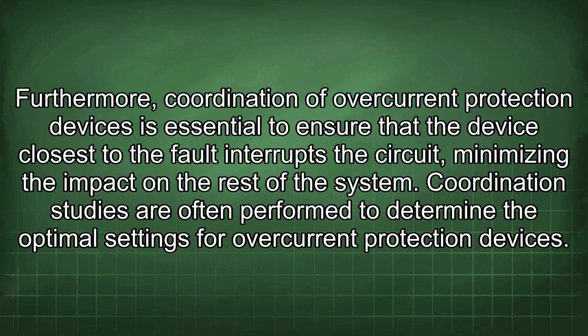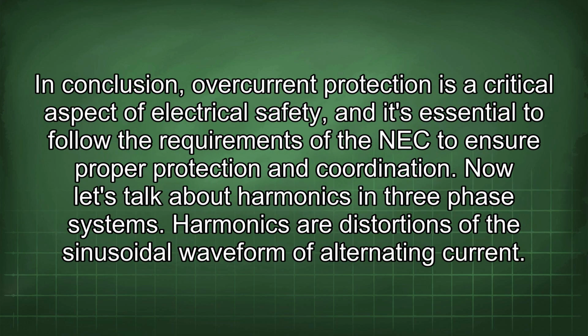Furthermore, coordination of overcurrent protection devices is essential to ensure that the device closest to the fault interrupts the circuit, minimizing the impact on the rest of the system. Coordination studies are often performed to determine the optimal settings for overcurrent protection devices. In conclusion, overcurrent protection is a critical aspect of electrical safety, and it's essential to follow the requirements of the NEC to ensure proper protection and coordination.